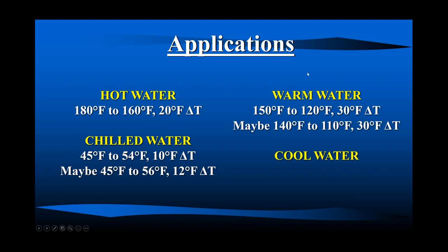And then there's cool water, right? Sensible only cooling. And that temperature is going to be 58 to 63, a 5 degree delta T system. Yeah, we just spoke about increasing delta T, but not this one. This one's going to decrease delta T and go from 58 to 63, staying below the dew point, but trying to cool off that space we're in. So those are our applications. Probably not going to get into hot water on our new design anytime soon. Chilled water, warm water, cool water is where we're going to dwell.